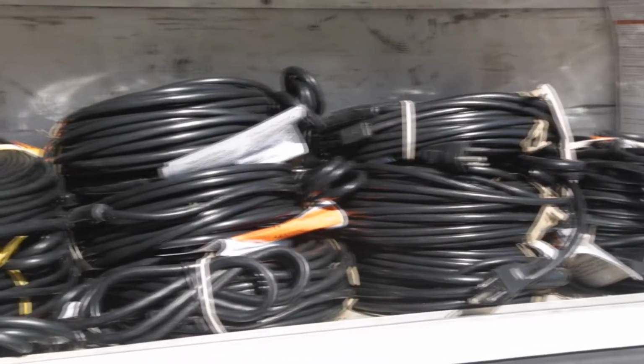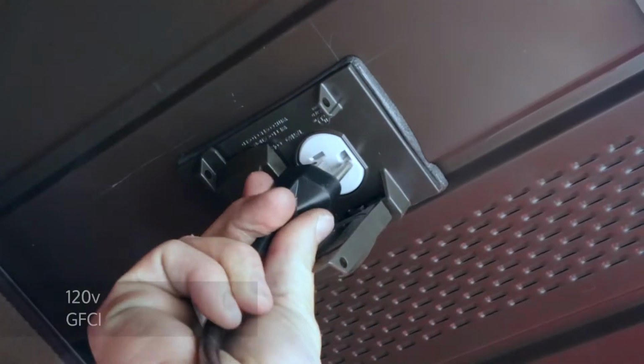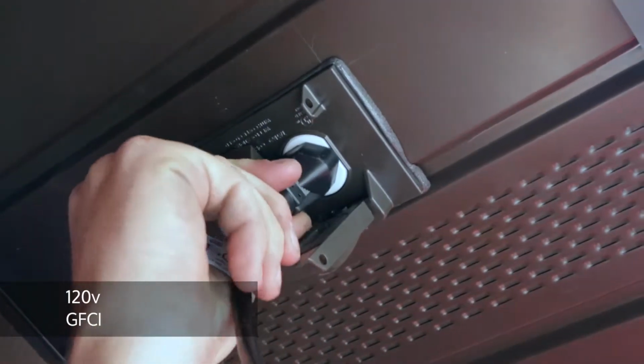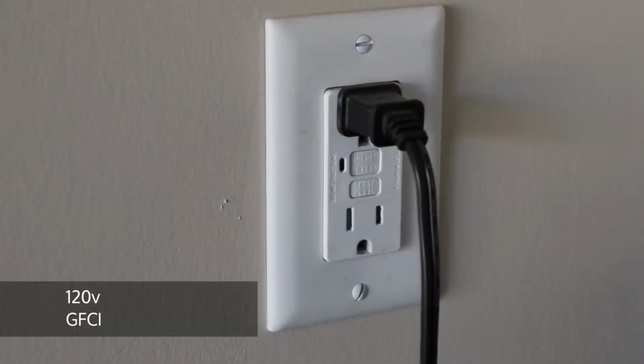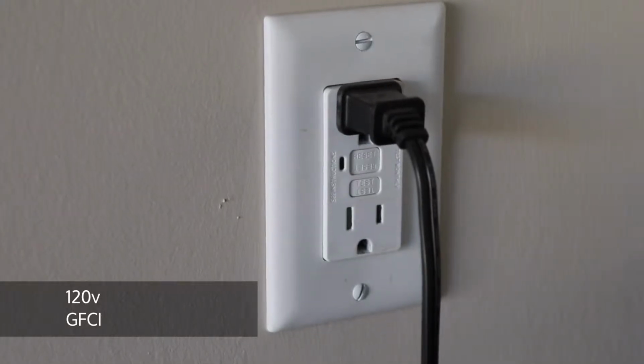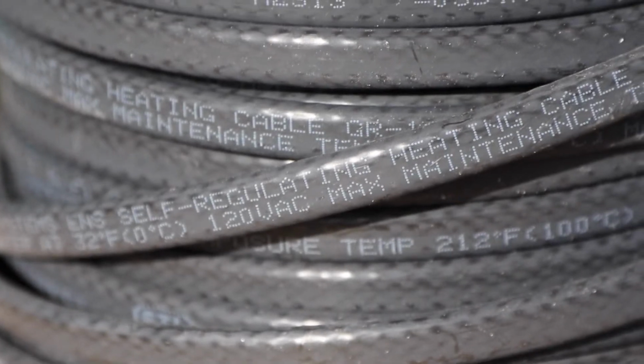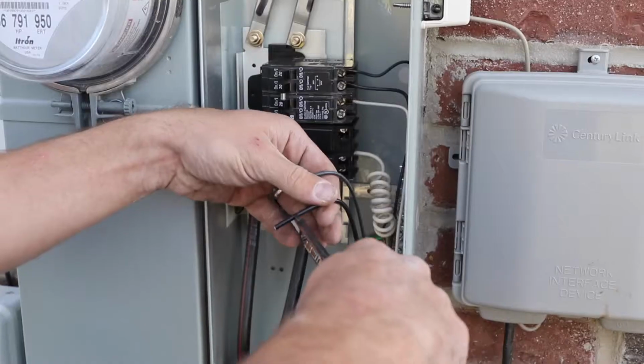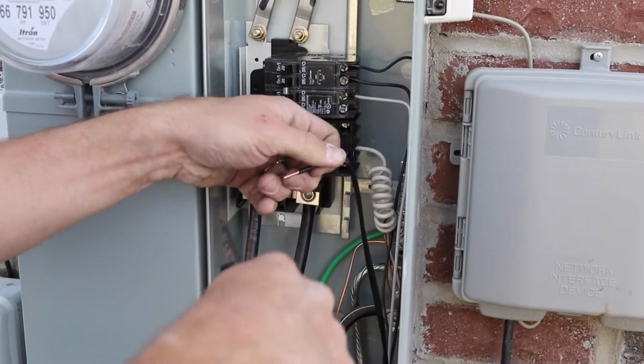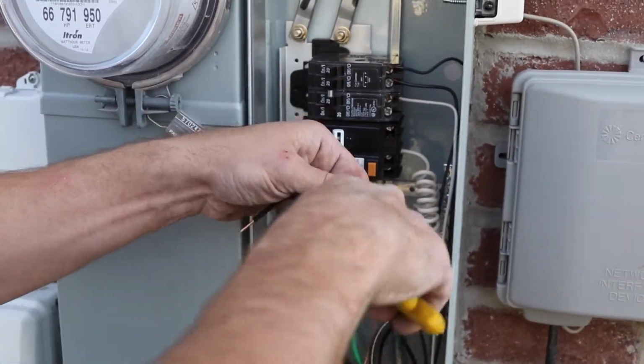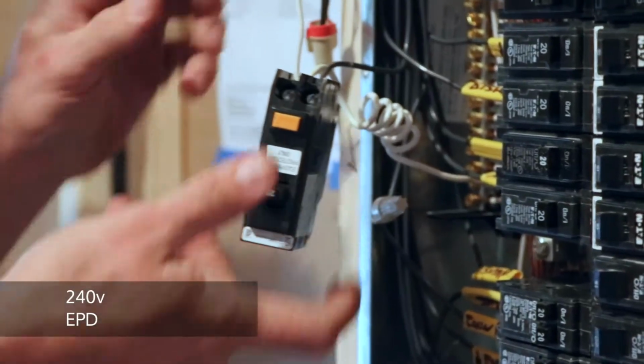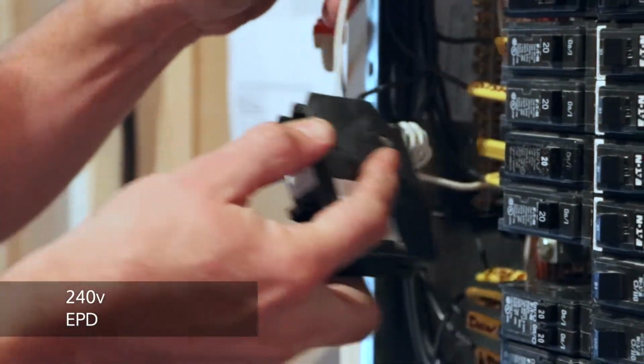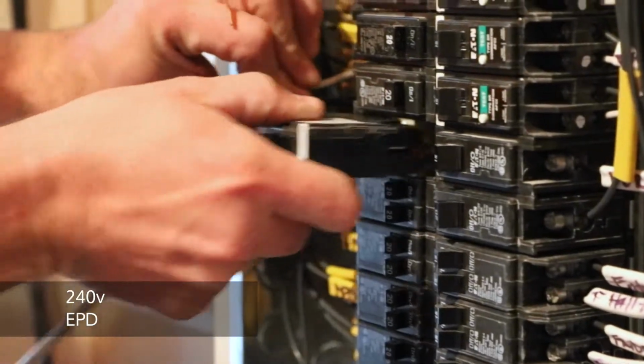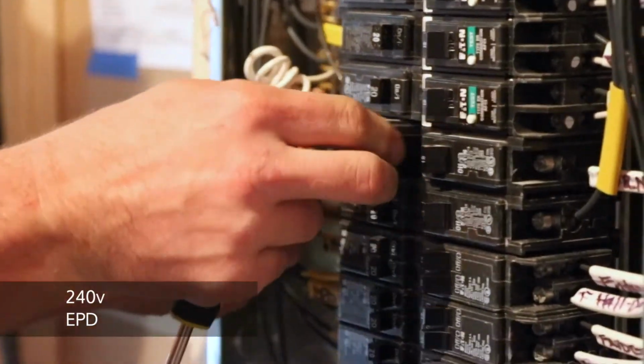Constant wattage heat cable generally requires 120 volt circuits and is recommended to have a GFCI in that circuit. GFCI is a ground fault circuit interrupter. Self-regulating cable can go 120 volt. It can also be a 240 volt, most commonly installed with a 240 volt circuit. Self-regulating cable acts differently than constant wattage. It requires an EPD breaker, equipment protection device. It's kind of like a GFCI on steroids.